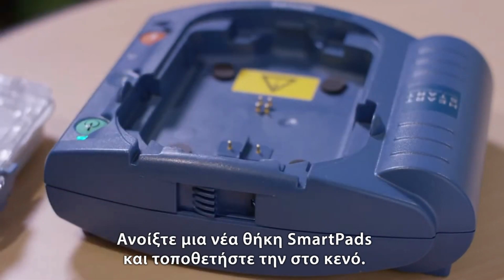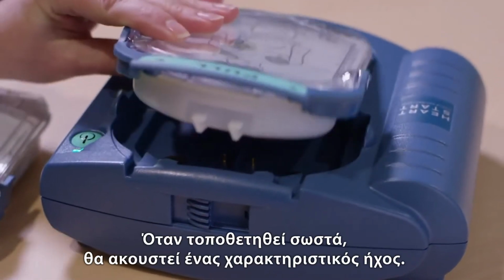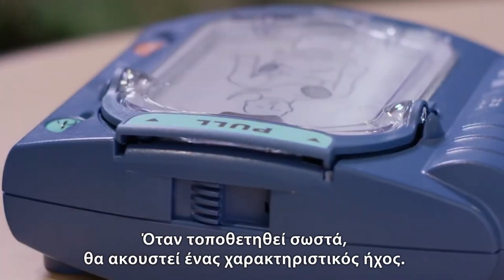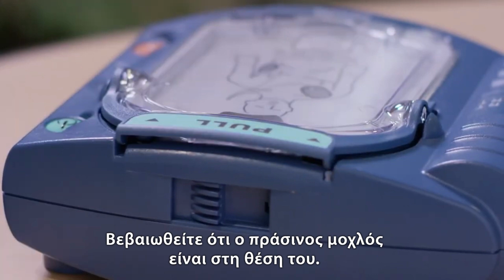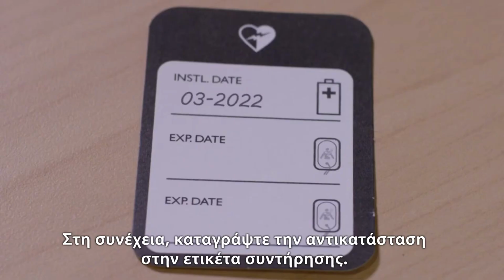Open a new smart pads cartridge and slide it into the cartridge recess. When the cartridge is properly placed, there will be an audible click. Ensure the green pull handle is all the way down. Then, record the replacement of the cartridge in the maintenance tag.